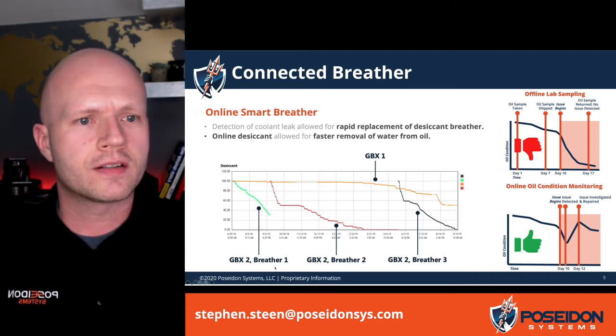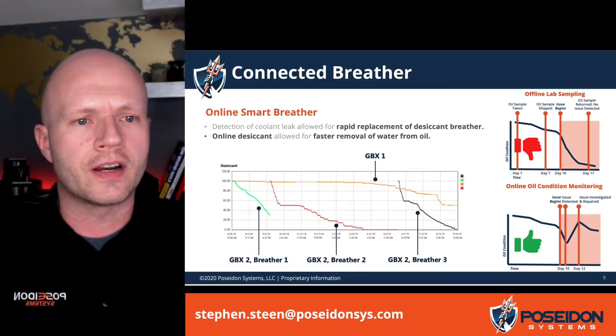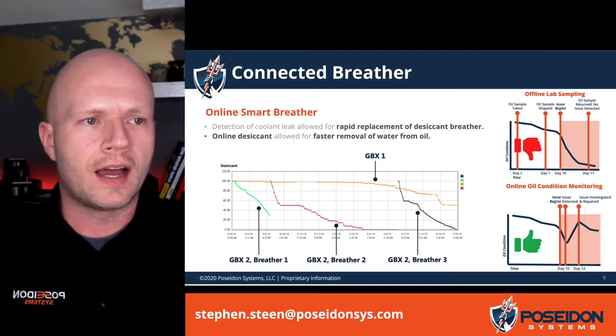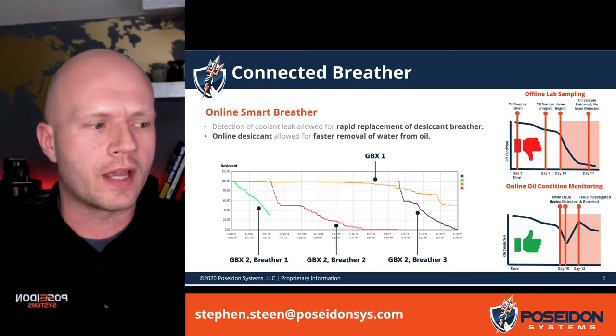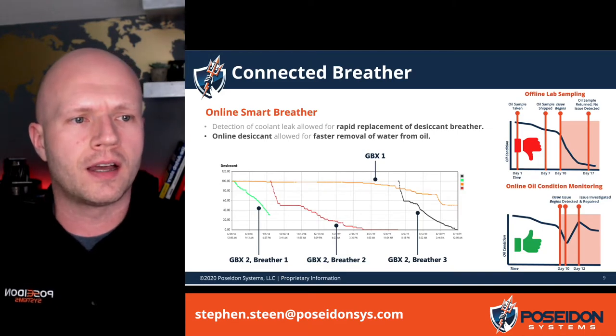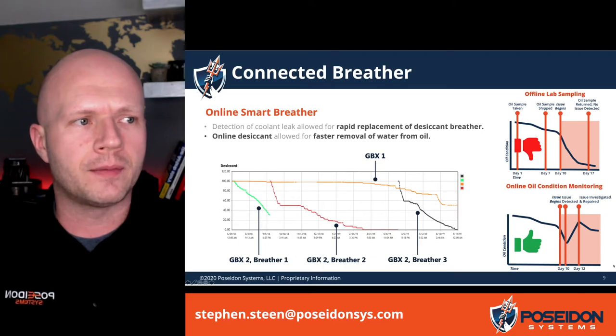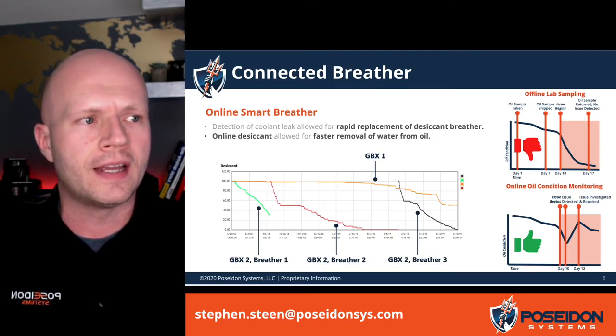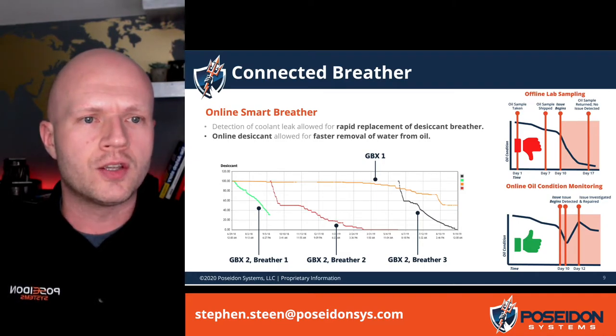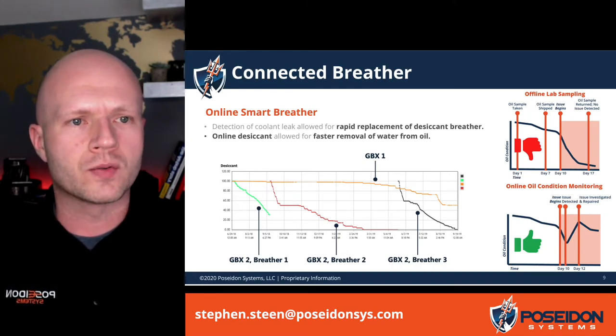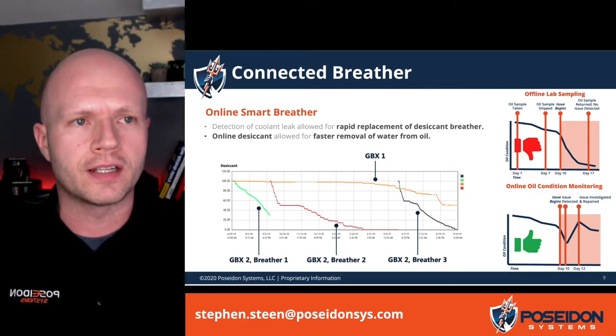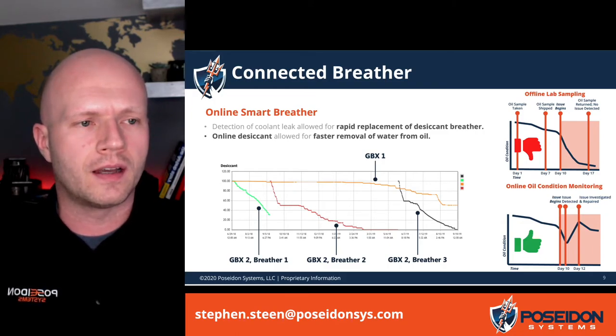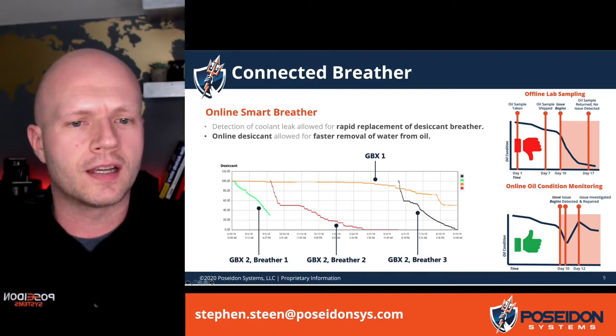Here's an example of connected breathers. This is a good example of two different gearboxes in the same location. In one case, the breather was very quickly losing its life by being used up by the humidity it was capturing, while the other gearbox very close by was not. This is a good comparison showing the value of not running pieces of equipment where the desiccant breather has been used up. Going to a condition-based replacement, you can really optimize and keep the humidity out of those pieces of equipment, since one might be completely different than another even though they're in fairly similar locations. This was also able to detect a problem with that gearbox that was eventually replaced, but the operator was able to replace those desiccant breathers in a timely fashion to keep the humidity lower.